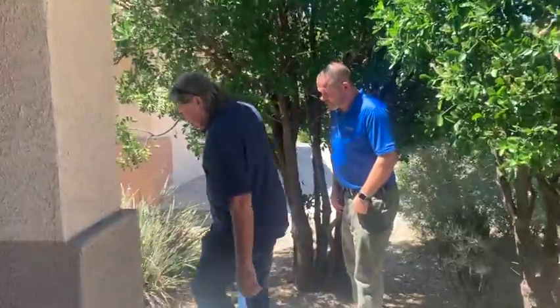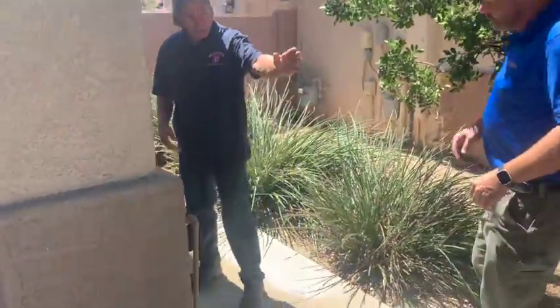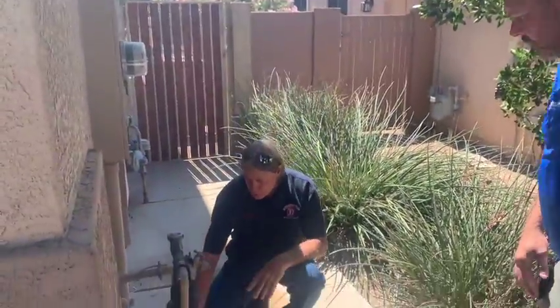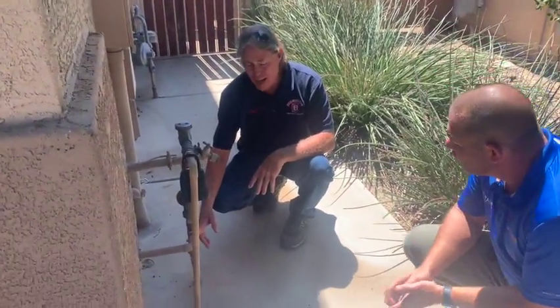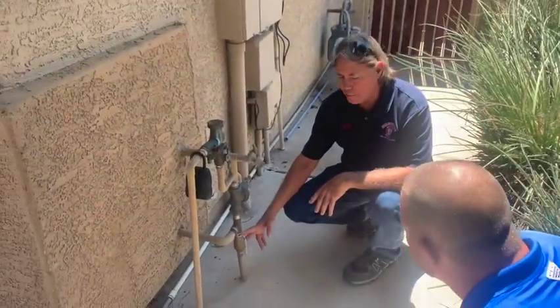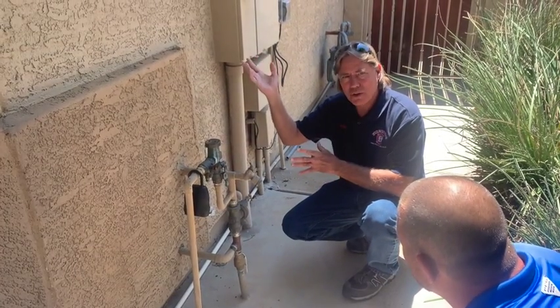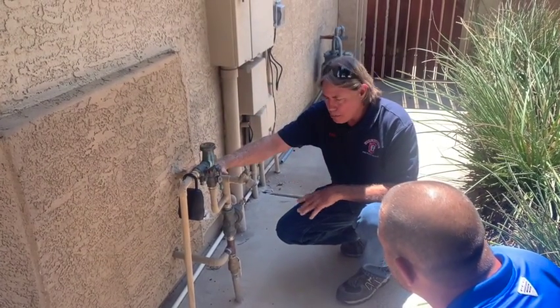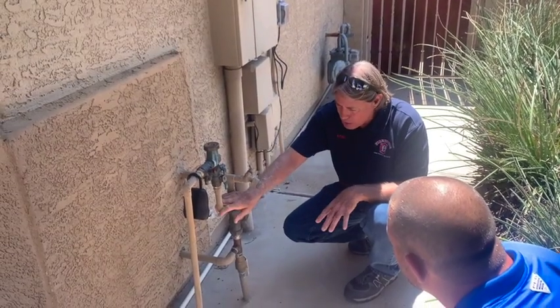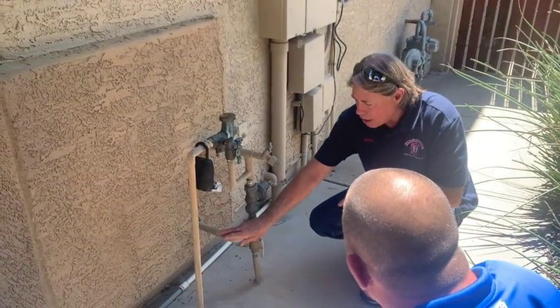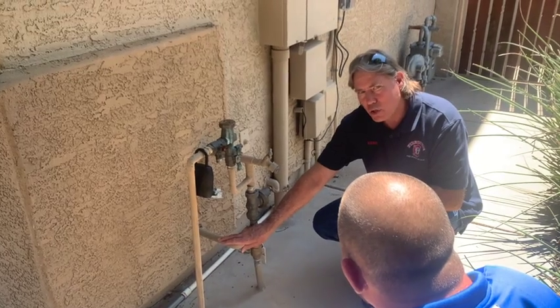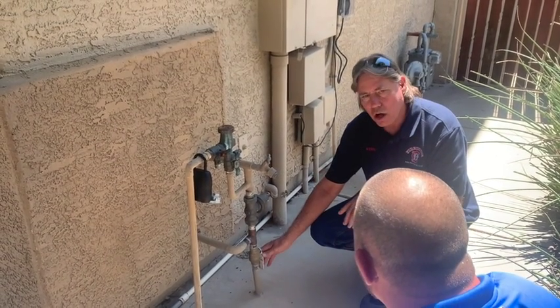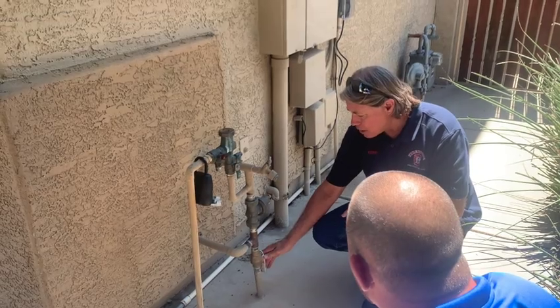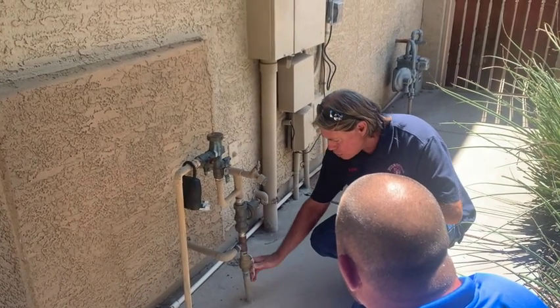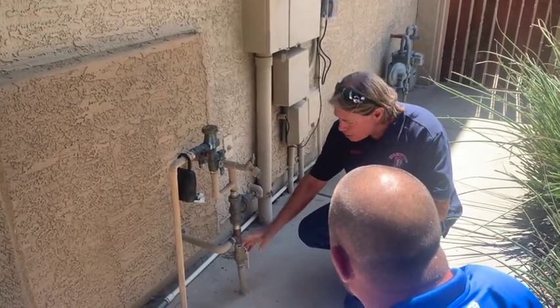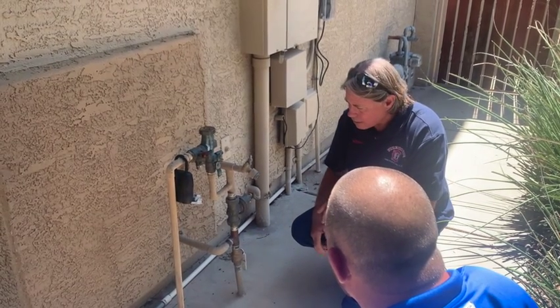Excellent. Now, typically on these systems, the water is going to come directly from the meter, and the first thing it's going to run into is a shutoff valve. We call this a combination or a main shutoff. So when folks have a problem in their home, either something with their domestic, something with the irrigation outside the home, or maybe a line in the fire sprinkler system might have started leaking, this is where they would shut it off. This is a combination shutoff valve. So we want to make sure that valve is working. So we want to operate it a couple times a year to make sure it's functional when you need it.